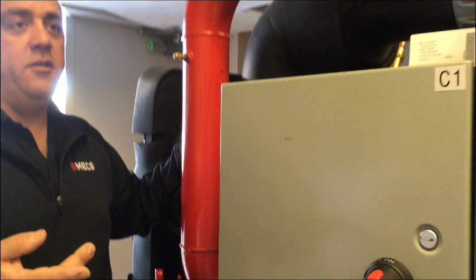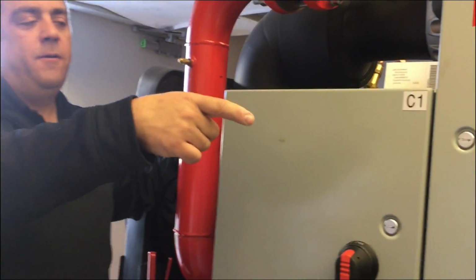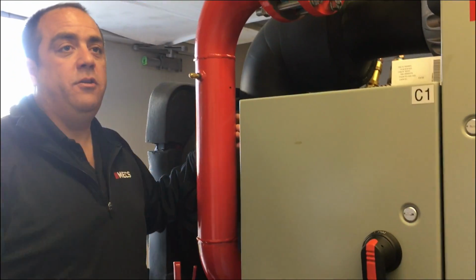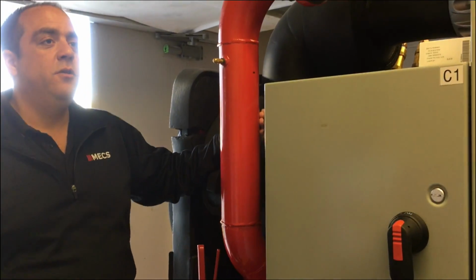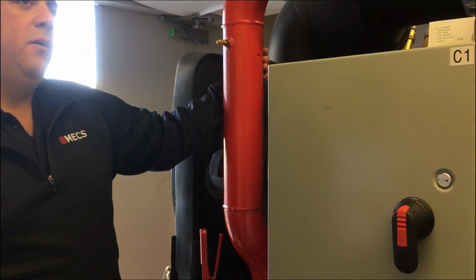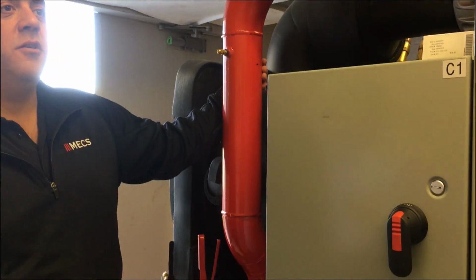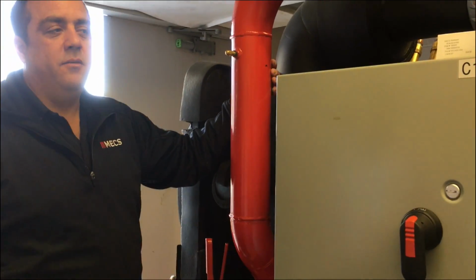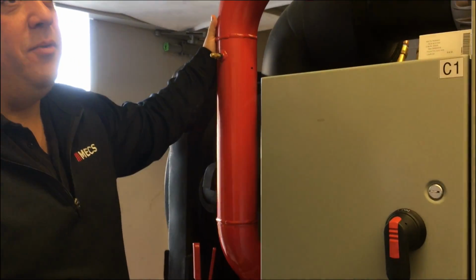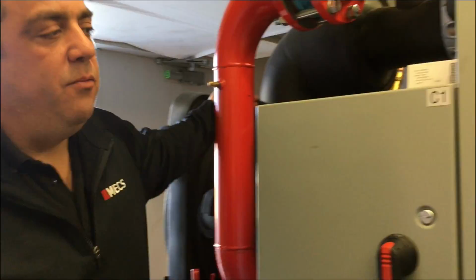Low pressure again is the third stage. There's a low pressure setting in here. Then there's a low pressure in each compressor that we can't lower. It's set at 22 pounds, and that one is at 15. Which basically, if that one trips, we're out of gas. So that's the last one, one of the last things we want to see happen here either.